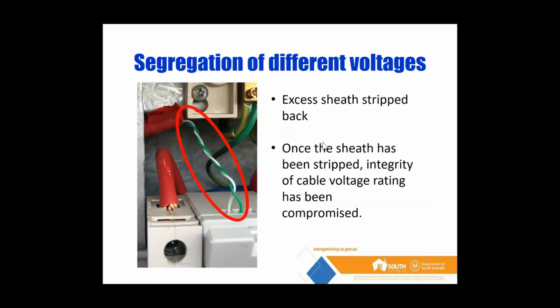Just to extrapolate a little bit on that, guys, stripping back the sheath on this cable is also another issue. Let's pretend that this cable is rated for the highest voltage present. What is done here isn't compliant. The internals of this cable haven't been rated for the highest voltage present, and it could quite easily bend over and touch this low voltage single insulation, or flick out possibly and even touch the live conductive parts. Now, whatever this is connected to isn't rated for that type of voltage, so it's not compliant.